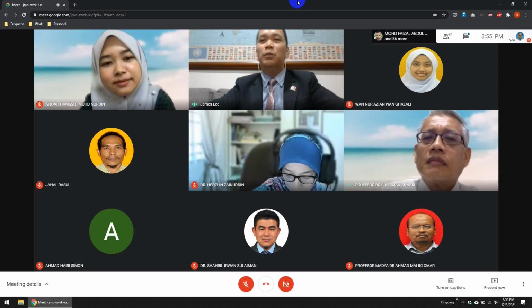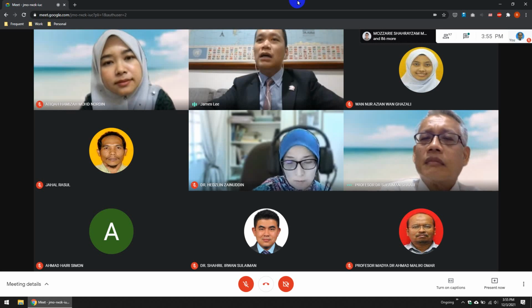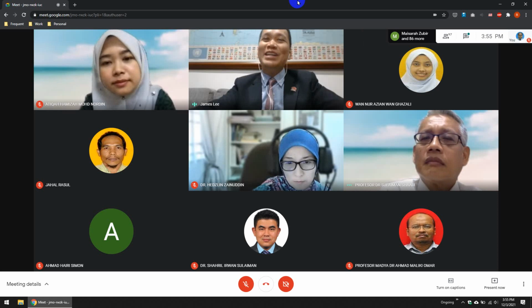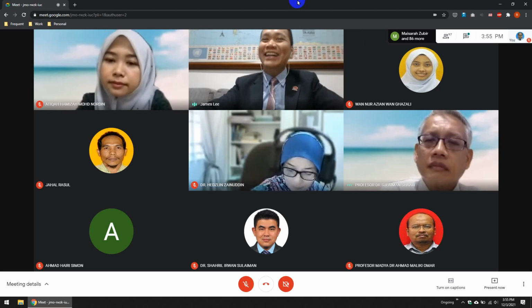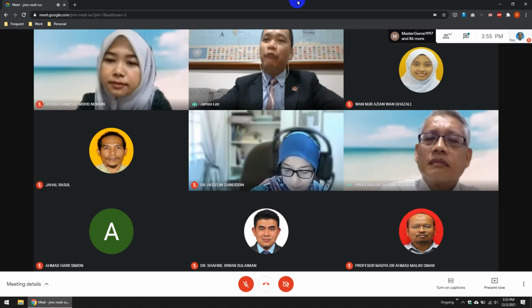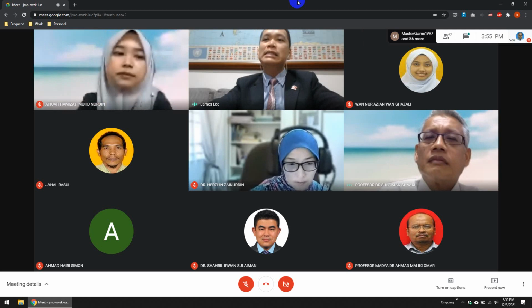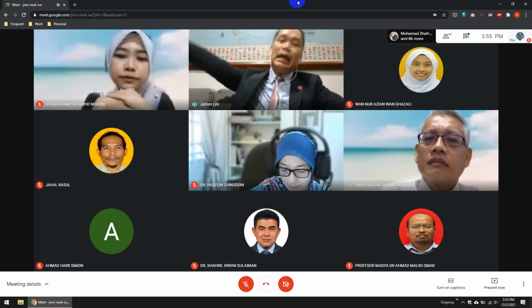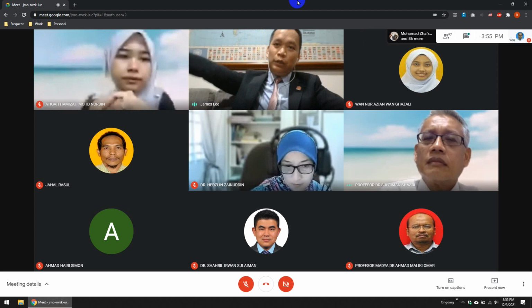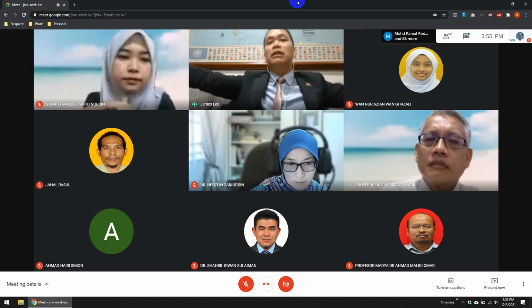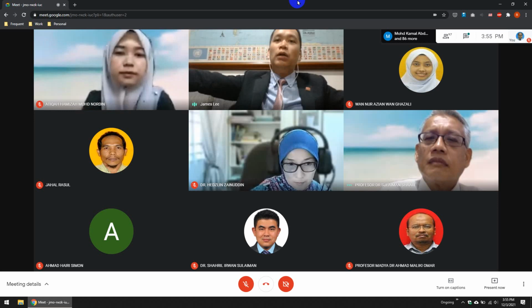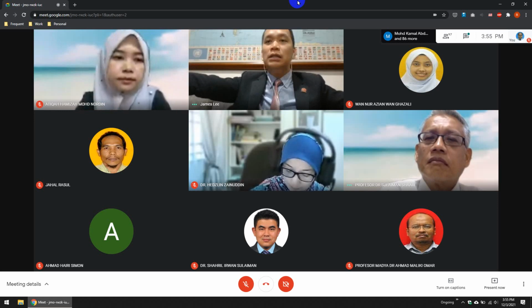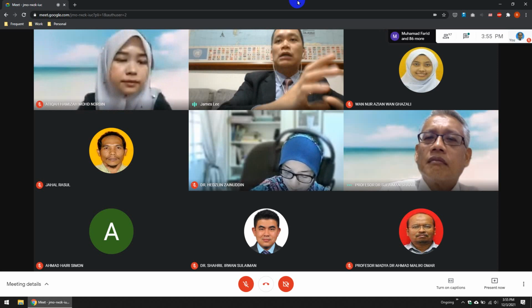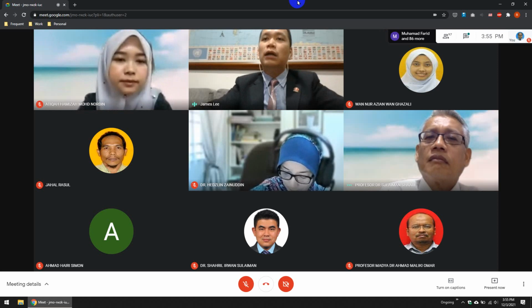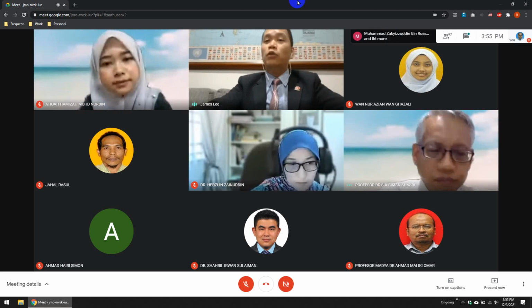SPDs, should we add additional ones? So this is the part where I think MS1837, I'm trying to update this, because we believe there's no additional requirement for DC and AC SPDs. Only at the MSB level, yes, please go and put another SPD there, because we're trying to protect different sides of the cable as well as the components. But in and of itself, our SPD in terms of AC and DC are capable of withstanding, as you saw from the video earlier.